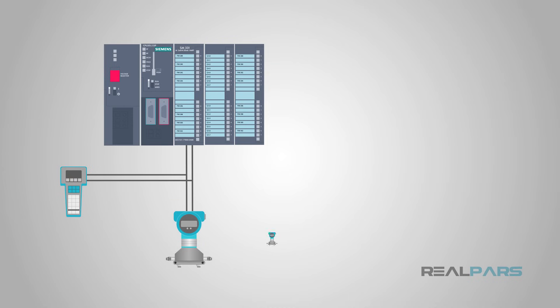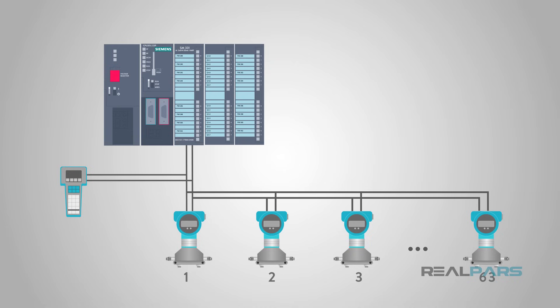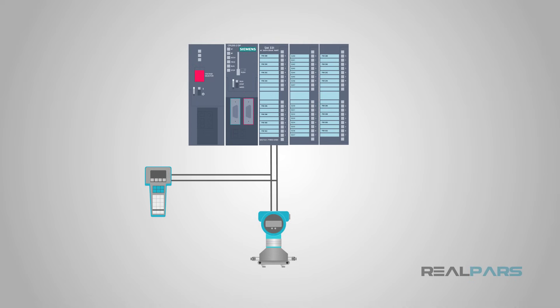Networking HART devices in most control systems applications is not practiced. Because of its limited speed and its cumbersome multi-drop network topology, we generally assign only one node or sensor to each HART signal loop.